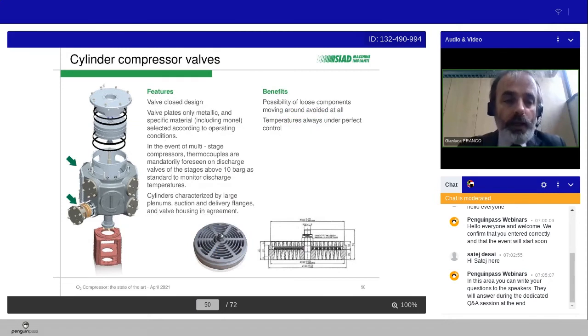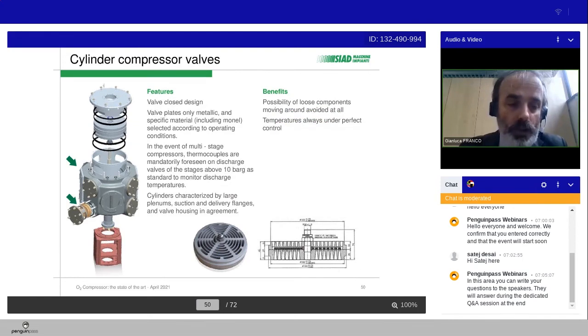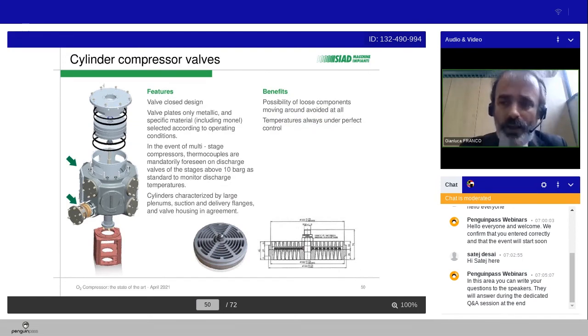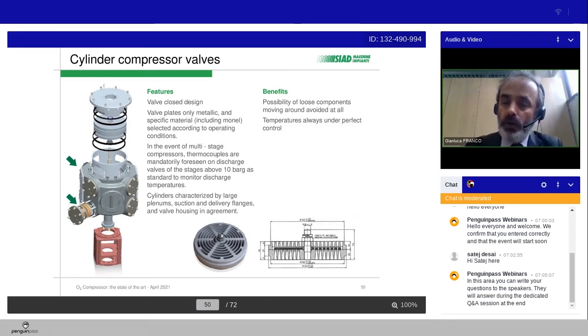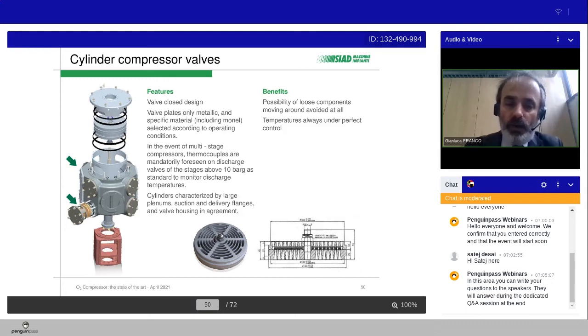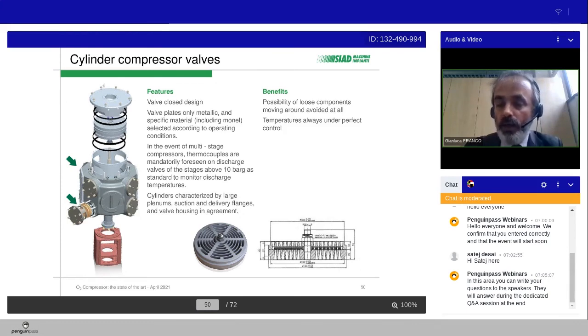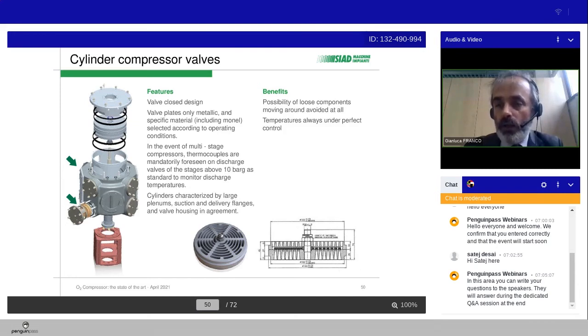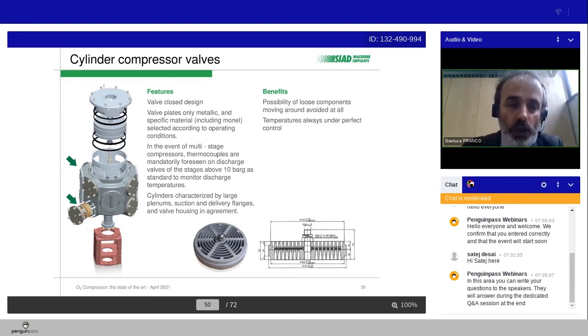A critical component of this kind of machine are the valves. Frankly speaking, I can tell you that 35-40% of one reciprocating compressor failure, statistically speaking, is due to the compressor valves. Because the valves are very critical components, they are subject to vibration, resonance, stress, and fatigue. So sometimes they can break.